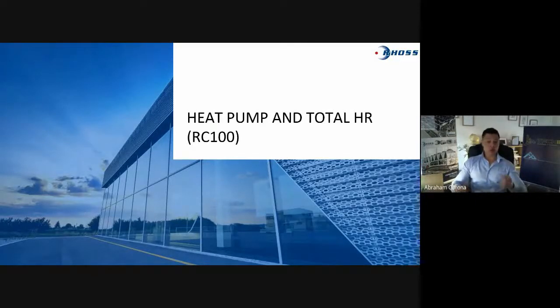The problem is that you're saving a lot of money in control type, in four-way valves, in all the accessories you need to do the reverse cycles and do everything. Yeah, and a standard reversible heat pump with heat recovery will be cheaper. Actually, this contractor was about to send the order to us because we were more cost effective. But yeah, we are really cost effective as a brand. We know what we're doing. But it was too good to be true.